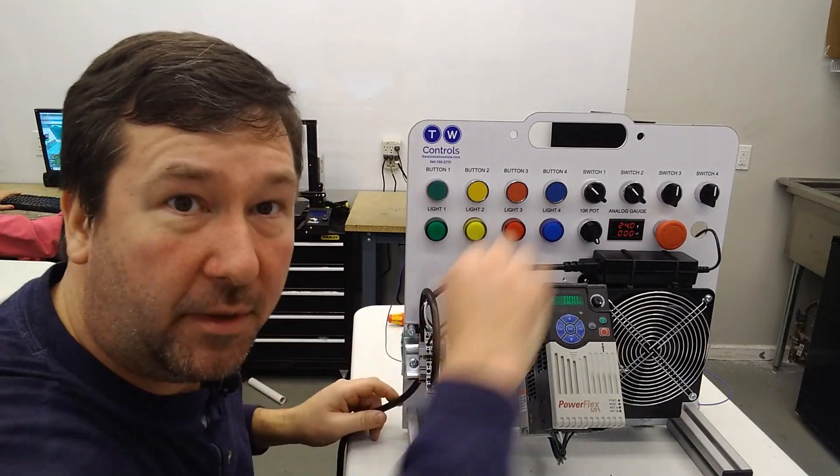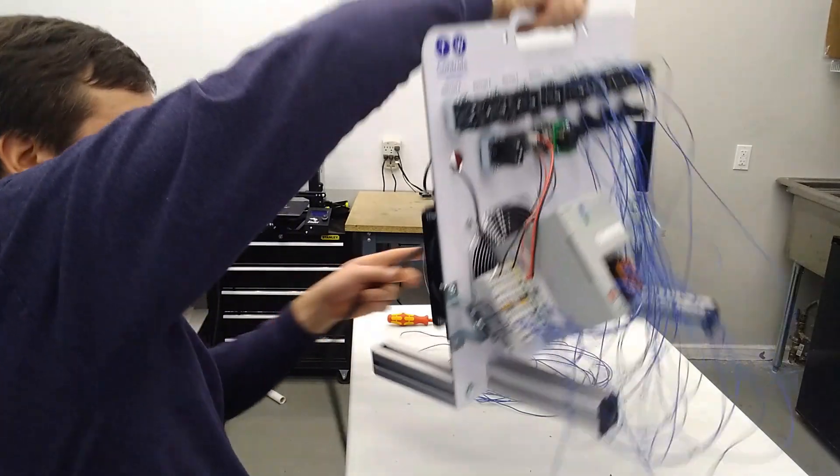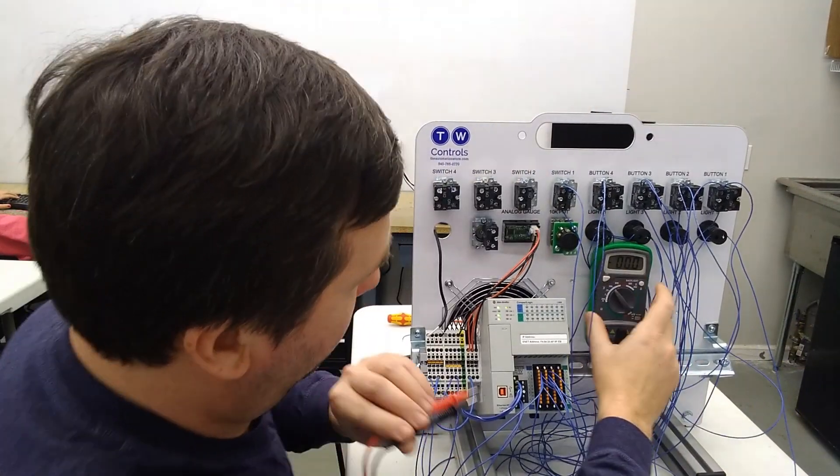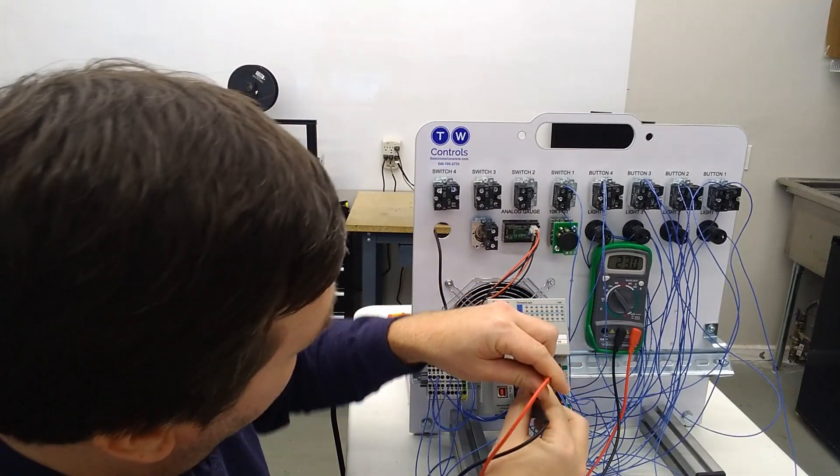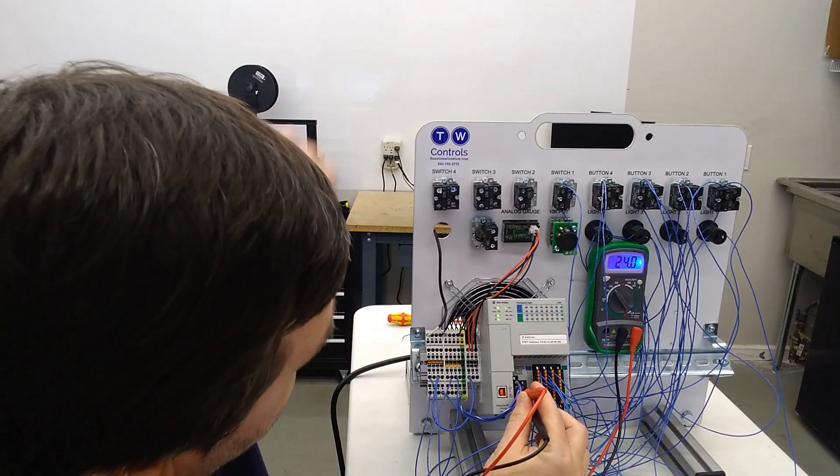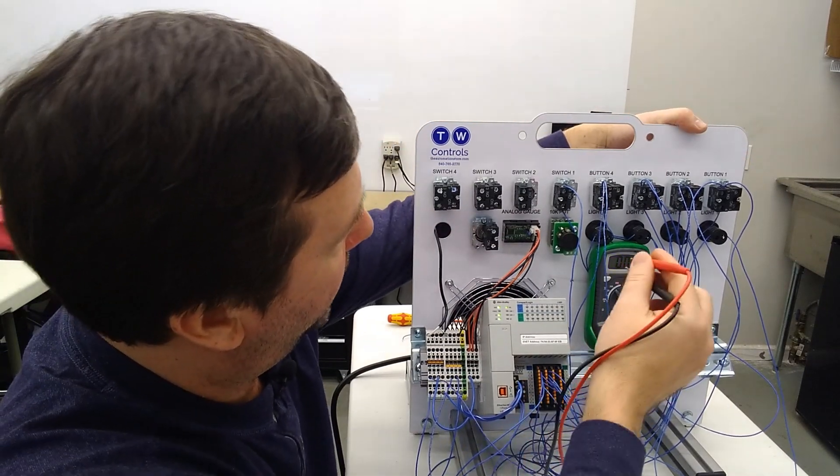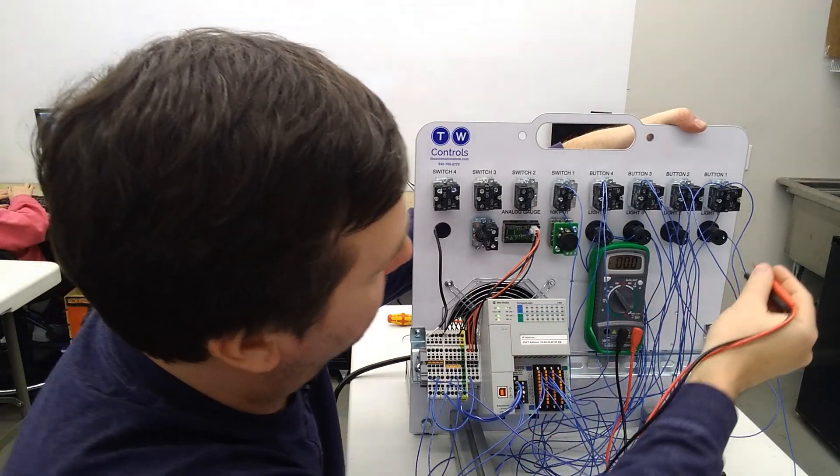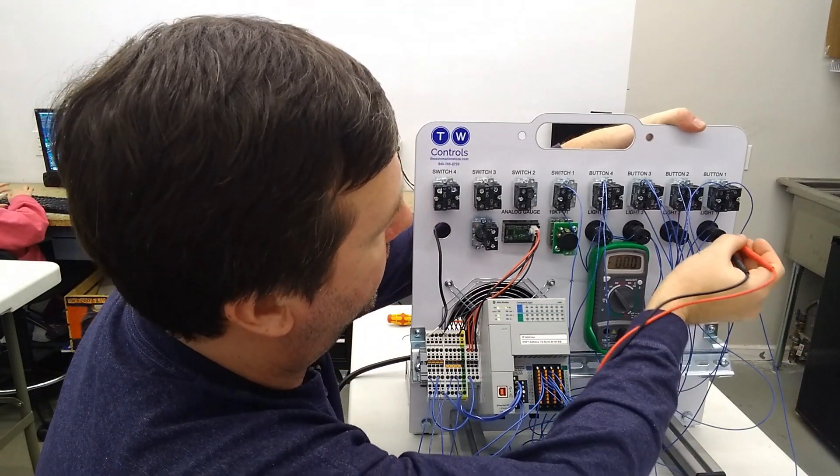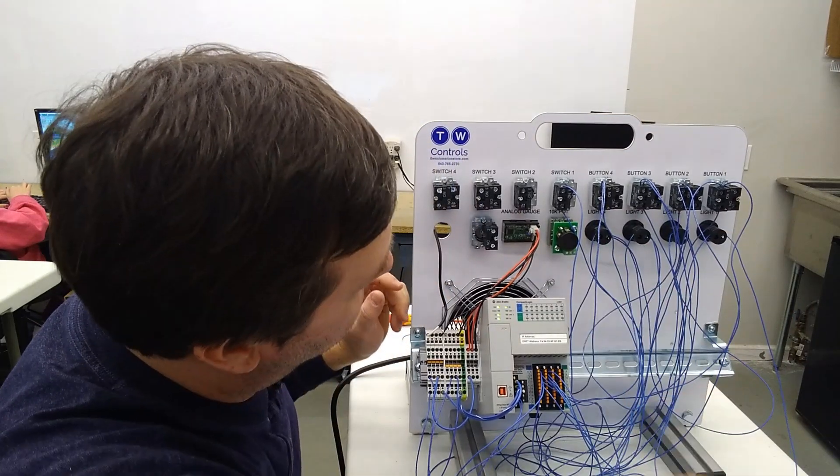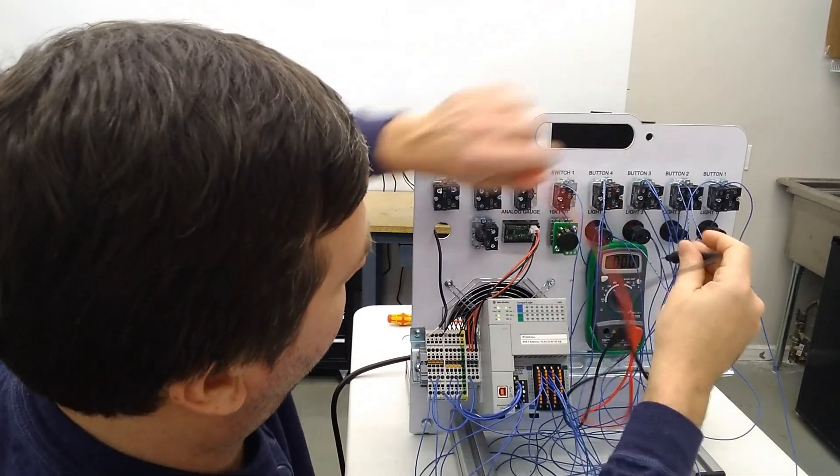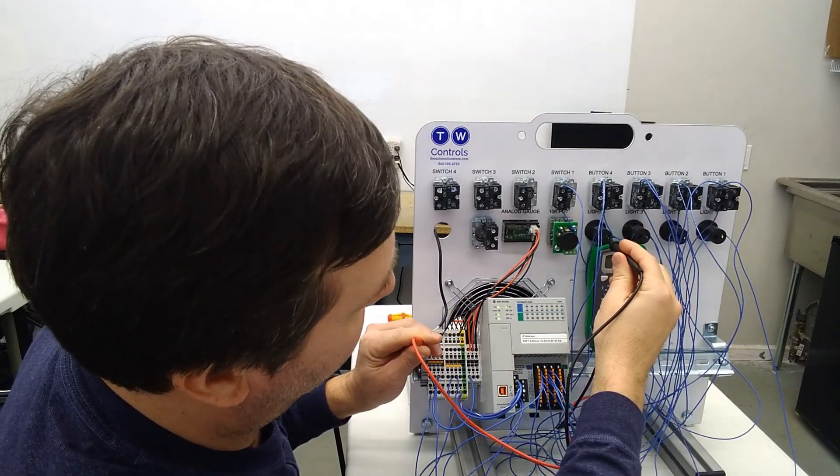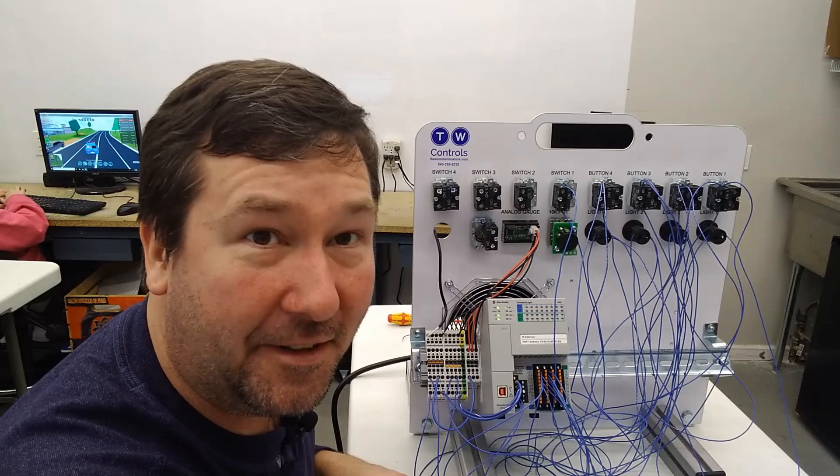Well, it looks like we have a learning opportunity. So let's see where I went wrong. So at this point, in between our FP plus and our FP minus, we should have 24 volt and we do. So when I switch button one, I am seeing the input going on, I'm seeing an output. So let's check across light one. And we have no power. So my guess is there's something wrong with my common. So I'm just going to go from the plus 24 and I'm going to check this light. Oh, we have 24 volt there.